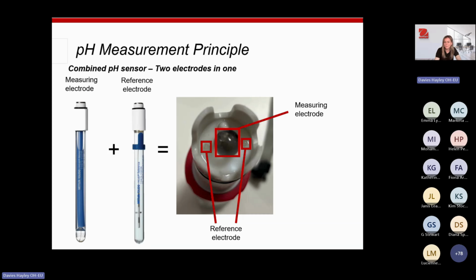In the past, there may or may not be anybody that would remember, way back when, you would require to have two separate electrodes. So you would have one measuring electrode and you would have one reference electrode. But now, with the improvement of manufacturing techniques, most modern sensors are combination electrodes, which simply means that both of the components, the measuring and the reference electrode, have been squeezed into a single body.